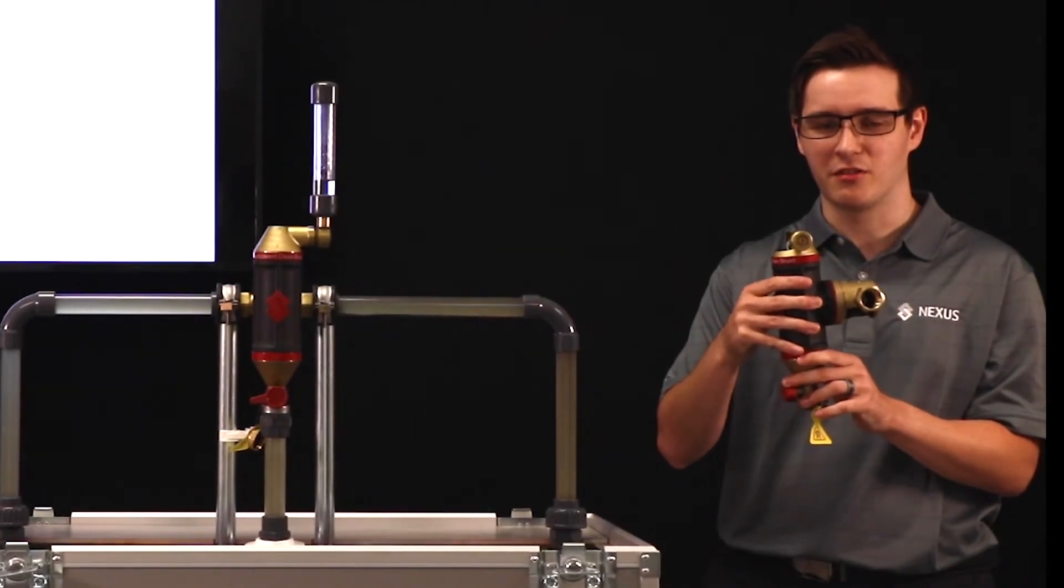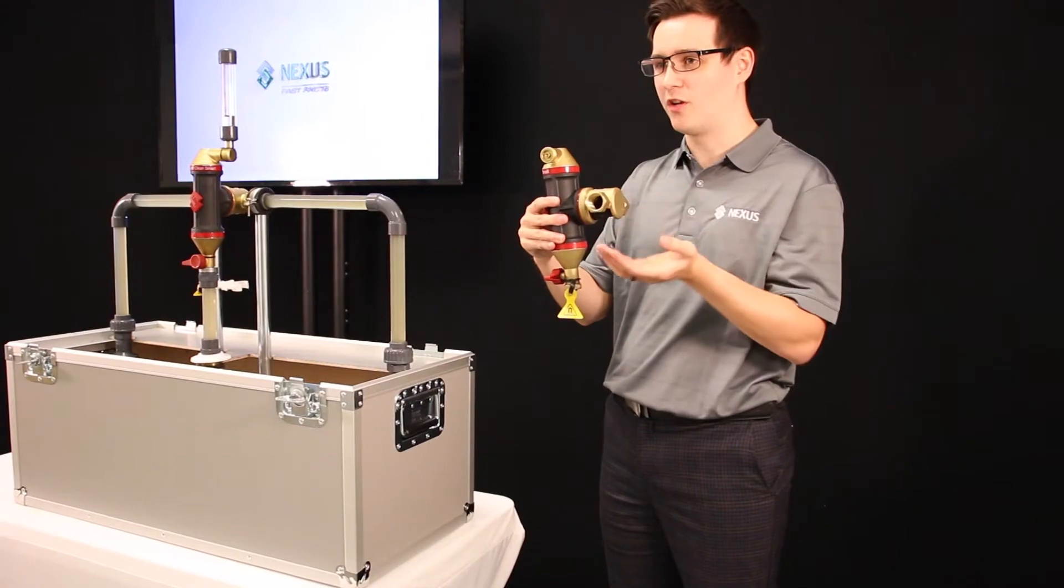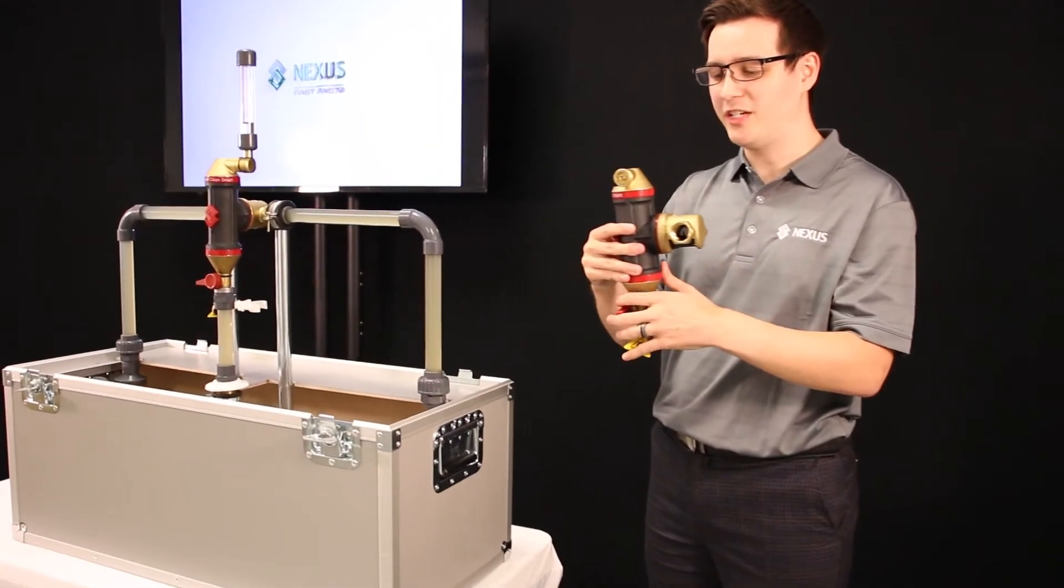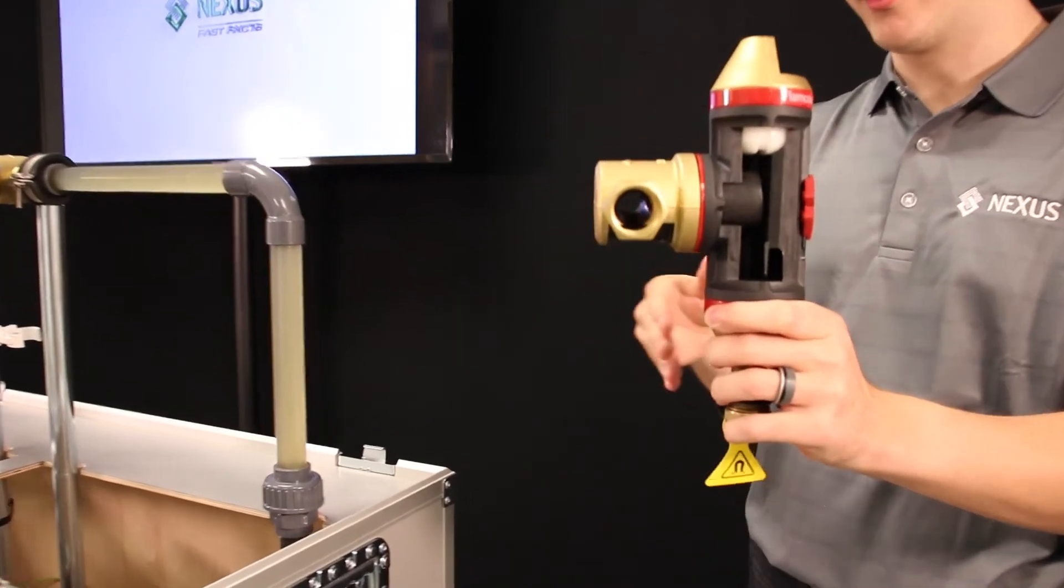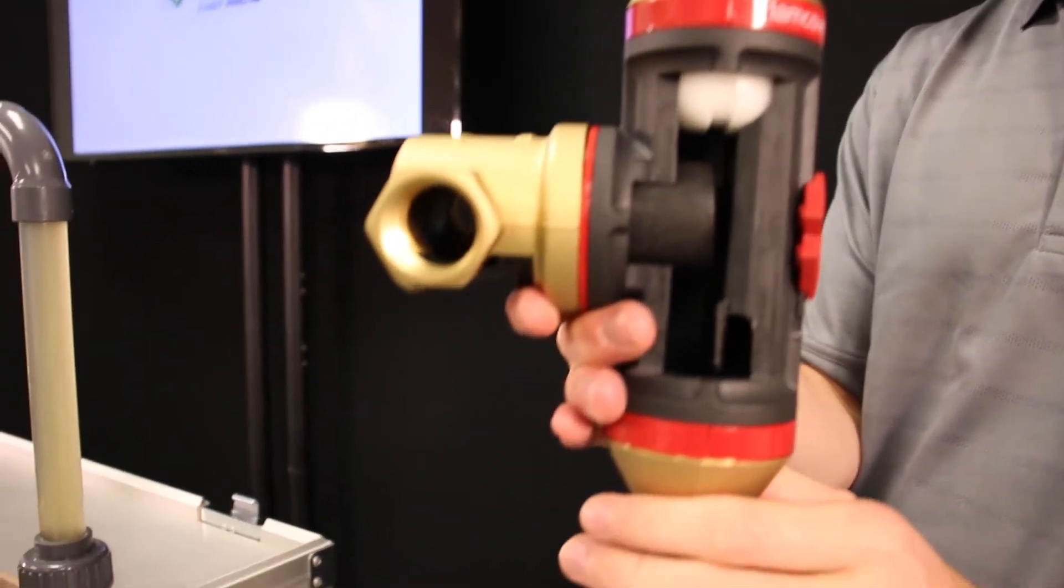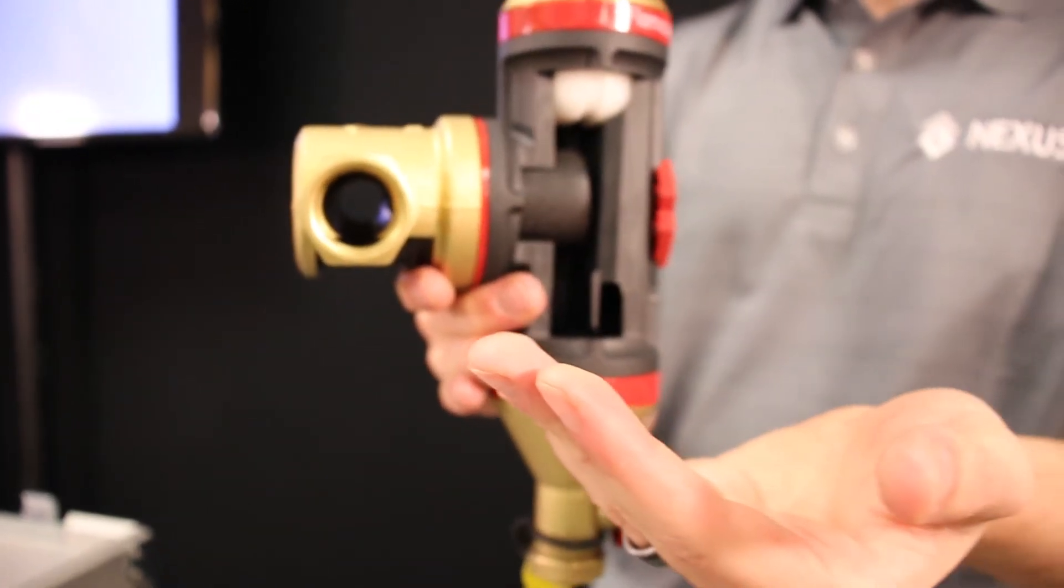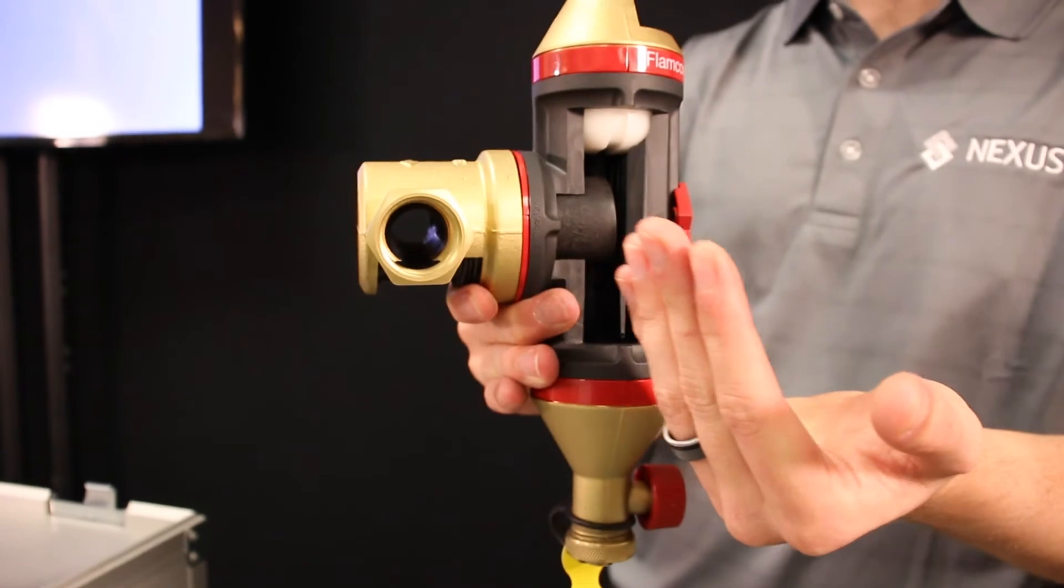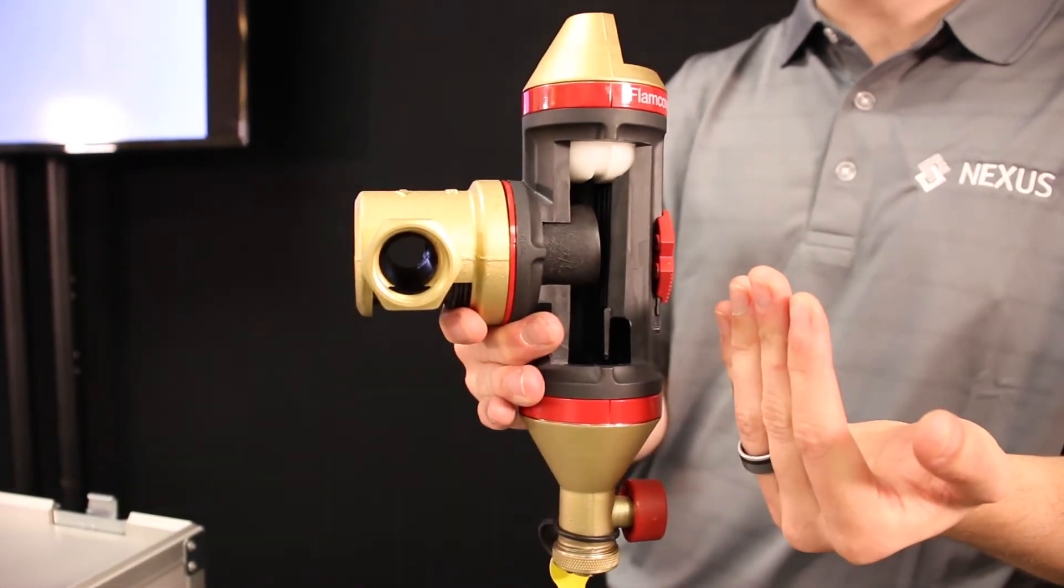It's there to slow the water down and allow the air to group to the top and the dirt to fall to the bottom. What's unique about the Clean Smart is that if you take a look through the pipework, there's little to no restriction there. So as the water goes through the pipework, it basically separates 10% of the water and that's enough to capture 40% of the air and the dirt.